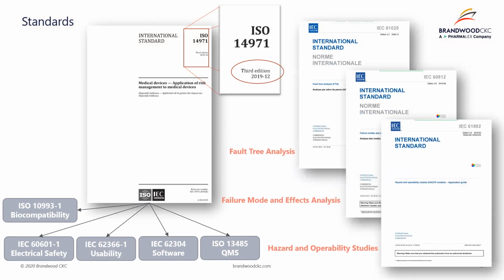Though the standard does not provide details on specific risk analysis techniques, there are a number of additional standards that can be referenced for assistance in conducting the risk evaluation and analysis, such as IEC 61025 for fault tree analysis. This is a top-down exploration of contributing factors for hazard events. IEC 60812 for failure mode and effects analysis, also known as FMEA, which provides a bottom-up determination of effects of function, component, or subsystem failure. And IEC 61882 for hazard and operability studies, which determines how procedural and design deviations can occur and the effect of such deviations. These are just a few examples.